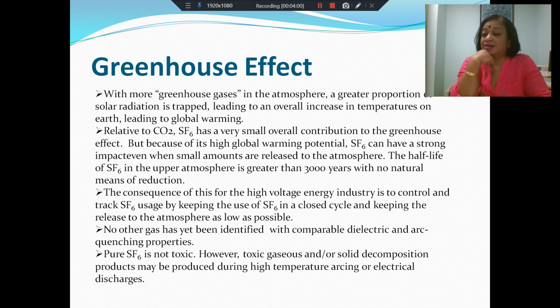Now the largest greenhouse gas, the greenhouse gas that is most detrimental to the Earth's ecosystem, is of course carbon dioxide, and it is being generated by all kinds of sources; even when we breathe out, we generate carbon dioxide. So if you compare to carbon dioxide, SF6 will have very little contribution to global warming because it is produced in very small quantities. If you consider the amount of CO2 that is being produced worldwide and the amount of SF6 that is being released to the atmosphere worldwide, it is very low. However, even very small quantities of SF6 have a high global warming potential. They heat to very high temperatures, and therefore, even if you have very small amounts released to the atmosphere, the impact can be much higher than even larger quantities of other gases.